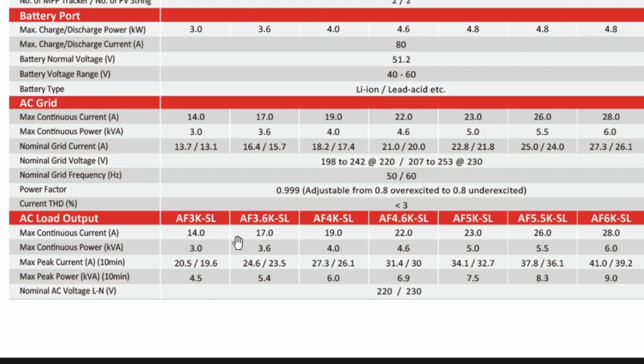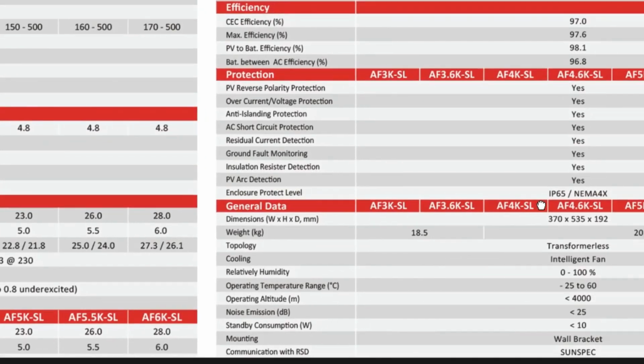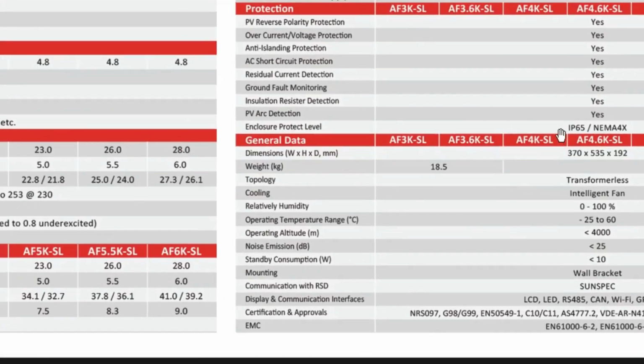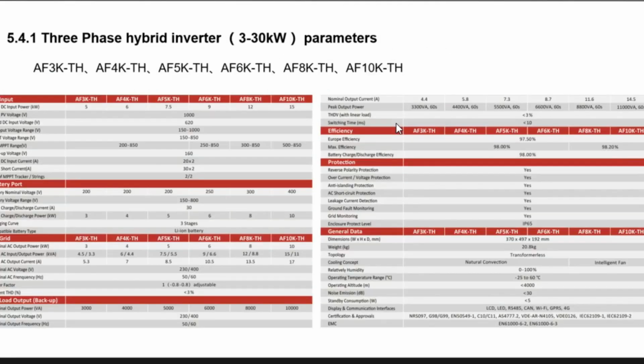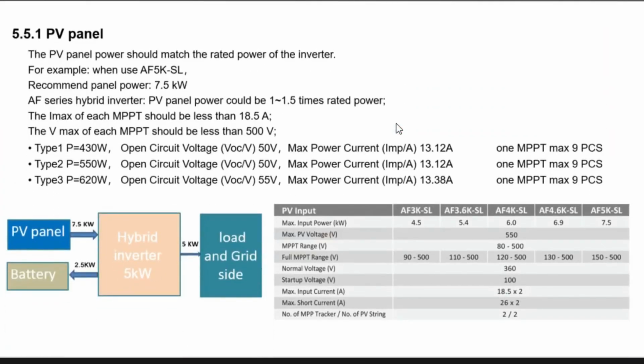During this time, especially for some motor loads, the battery can provide continued energy during the peak hour and then steady power, which makes the loads work smoothly when the grid is off. So that's a point that should be noticed during the system design procedure.